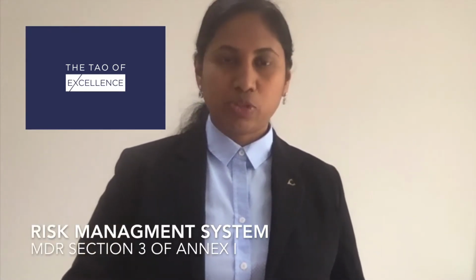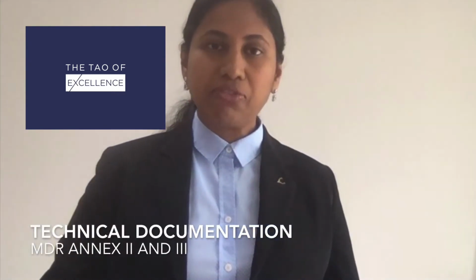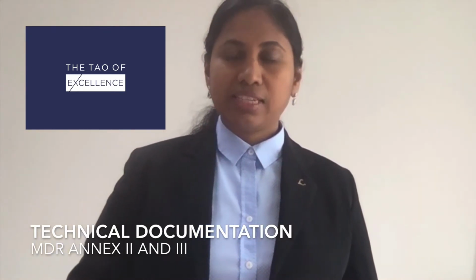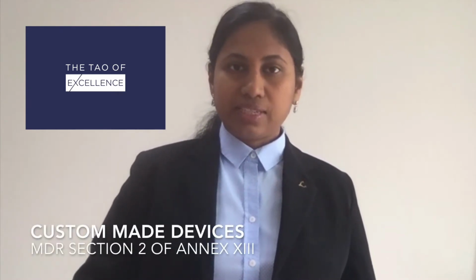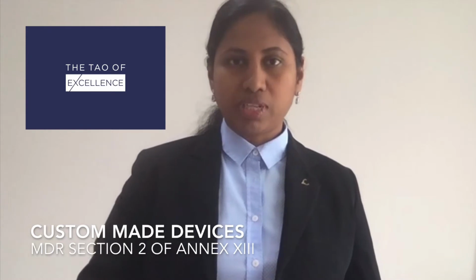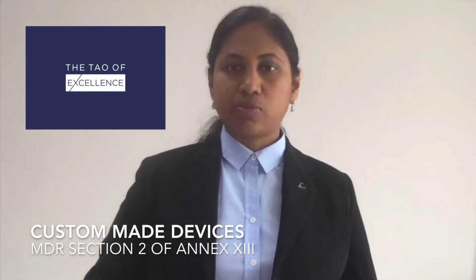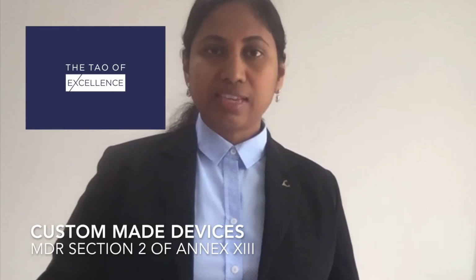The first system to be implemented and maintained is the risk management system, the details of which are explained in Section 3 of Annex 1. The manufacturer must carry out clinical evaluation, including the PMCF, which is explained in Article 61 and Annex 14. Manufacturers shall also draw up and keep up to date the technical documentation for these medical devices, which is explained in Annex 2 and Annex 3. The manufacturers of custom-made devices have to do the same for their technical documentation, and the details for these are explained in Section 2 of Annex 13.